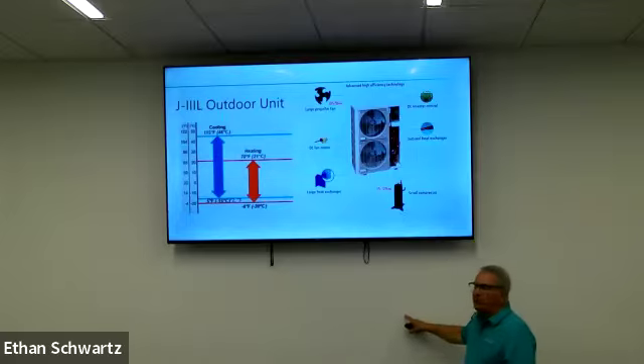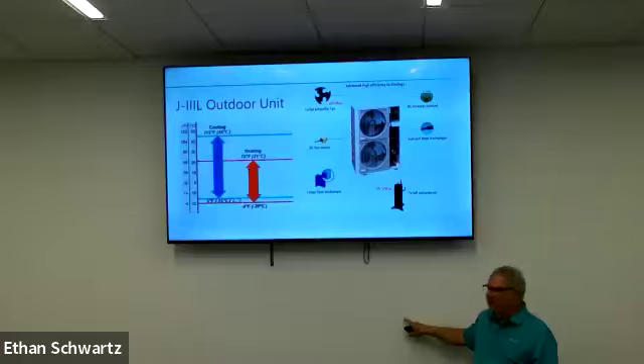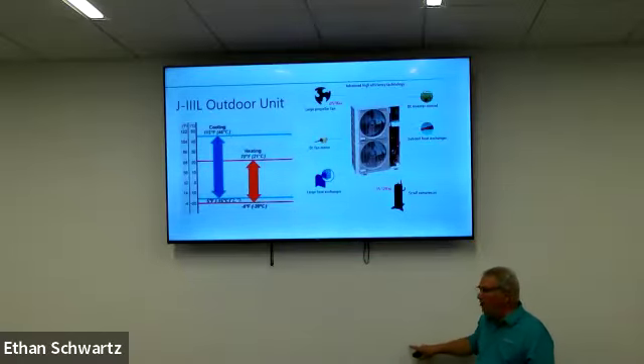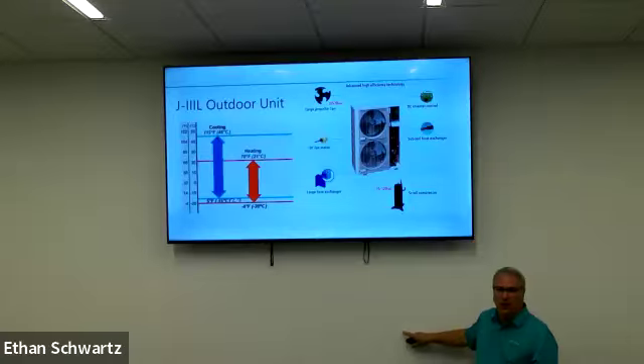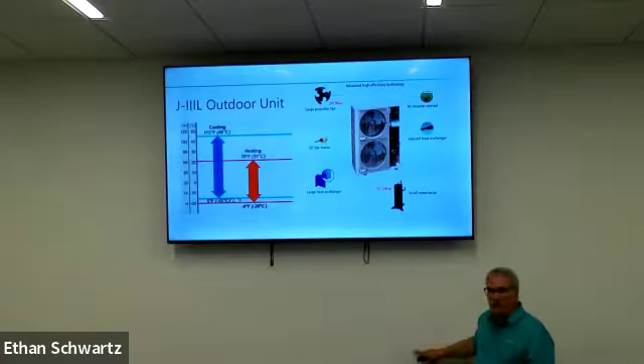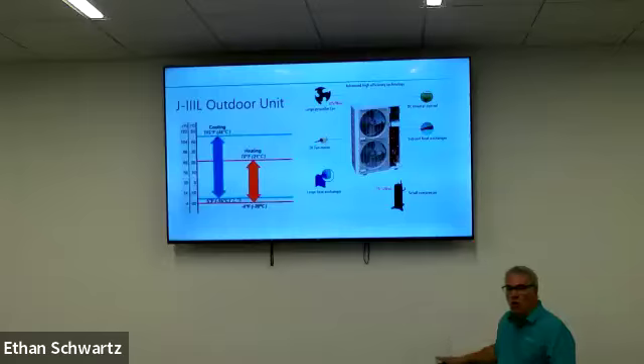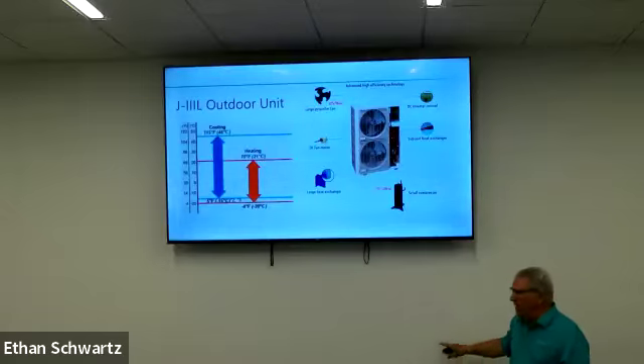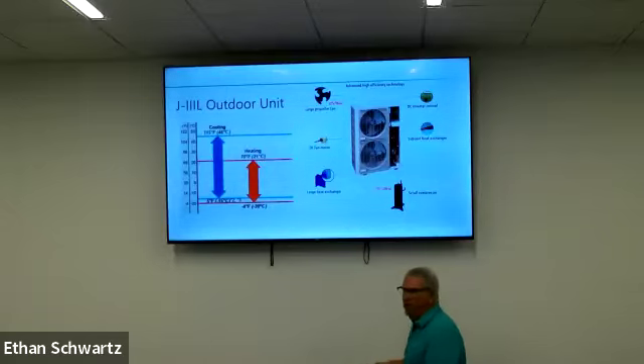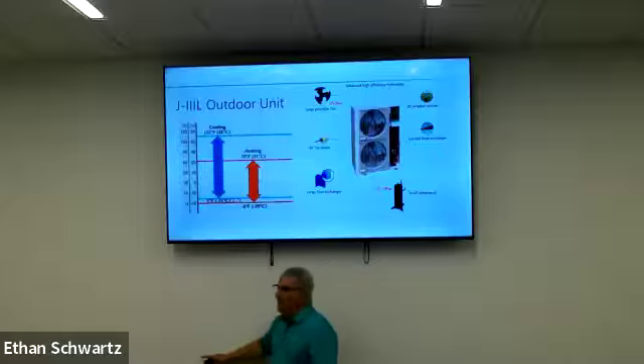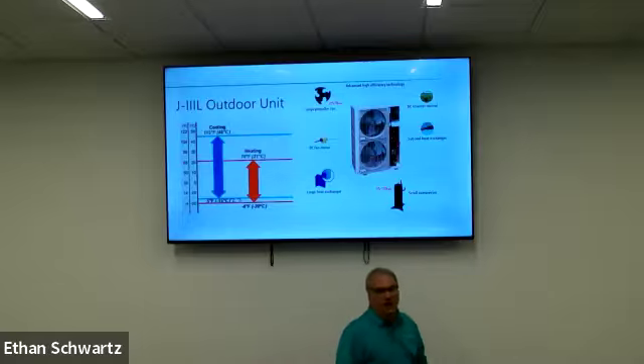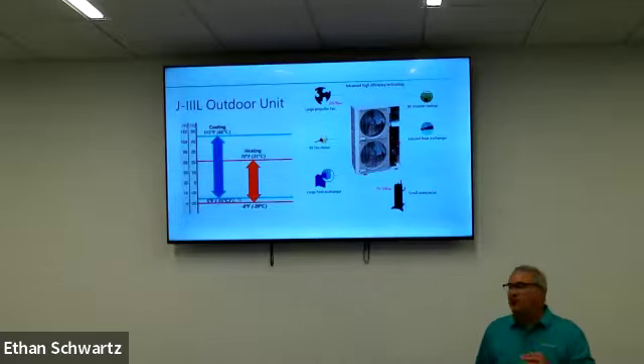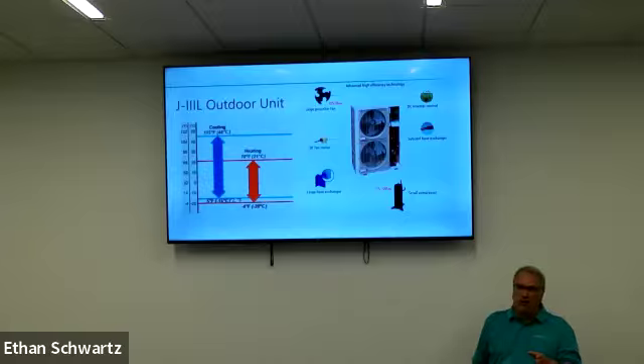When it finally reaches our indoor unit and there's not sufficient warm air or enough heat load coming across that wall mount, we are only going to do sensible cooling, just as if you were running water through that coil. Now we're coming back to the suction line where it should be gas, and we could end up liquid slugging the compressor.